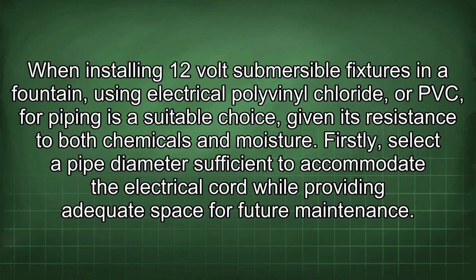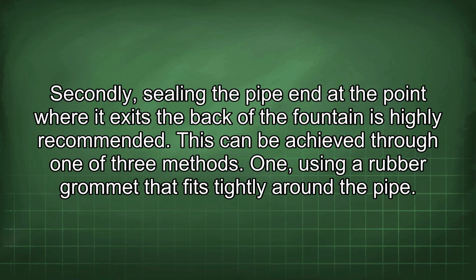When installing 12-volt submersible fixtures in a fountain, using electrical polyvinyl chloride, or PVC, for piping is a suitable choice, given its resistance to both chemicals and moisture. Firstly, select a pipe diameter sufficient to accommodate the electrical cord while providing adequate space for future maintenance. Secondly, sealing the pipe end at the point where it exits the back of the fountain is highly recommended.